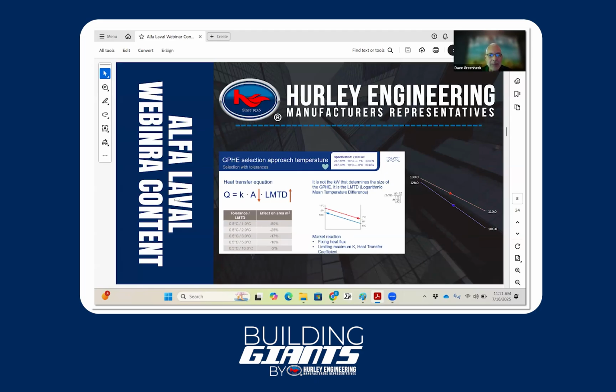The LMTD, log mean temperature difference, basically says that over the course of its path in counterflow, you're getting the most heat transfer possible. If it was parallel flow, you'd see something different: really good heat transfer at one end, not very good at the other. Counterflow gives a more even distribution, resulting in a significant increase, up to 10% or more, over parallel flow. That's why we do that.